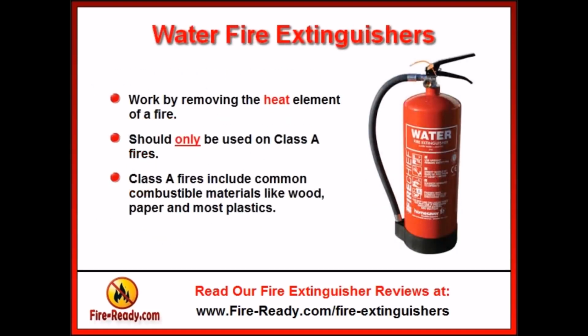Water fire extinguishers work by removing the heat element of a fire. These are for Class A fires only that involve ordinary combustible materials like wood, paper, and most plastics. These fire extinguishers should never be used on a Class B or C fire. Class B fires involve flammable liquids like gas, and using one on one of these could spread the flammable liquid and make it worse. Class C fires involve electrical equipment, and we all know that water and electricity don't mix.